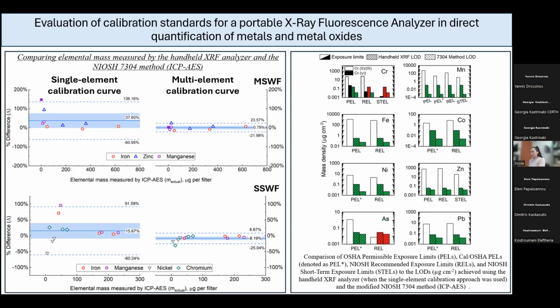In most of the metals, we see that we can successfully detect the exposure limits with any analytical method we use, except for chromium, specifically chromium-6. The recommended exposure limit of chromium-6 cannot be detected when we use the handheld XRF, while the short-term exposure limit of chromium-6 cannot be detected by either handheld XRF or ICP-AES. And also in the case of arsenic, the recommended exposure limit cannot be detected by either technique.